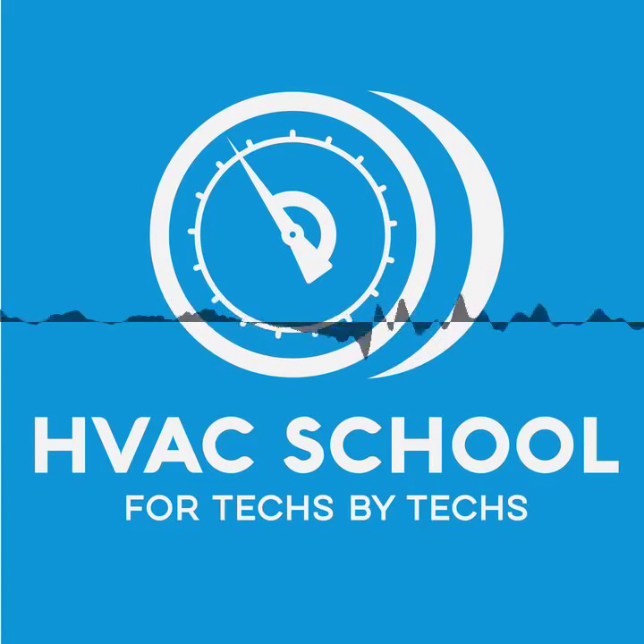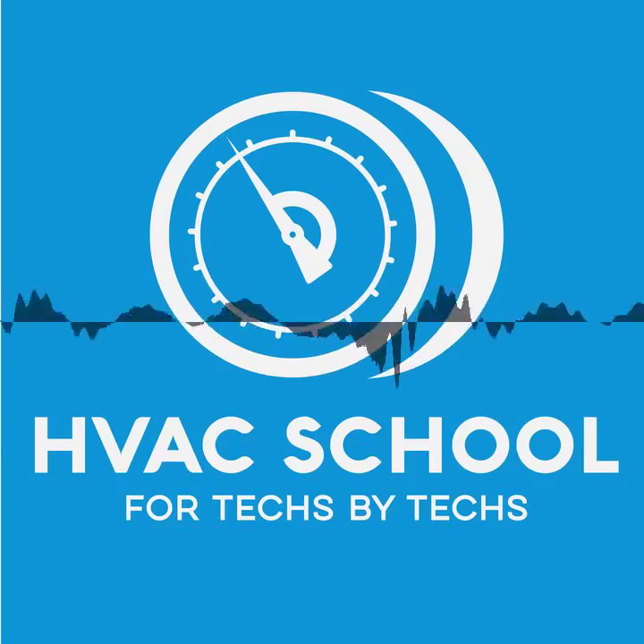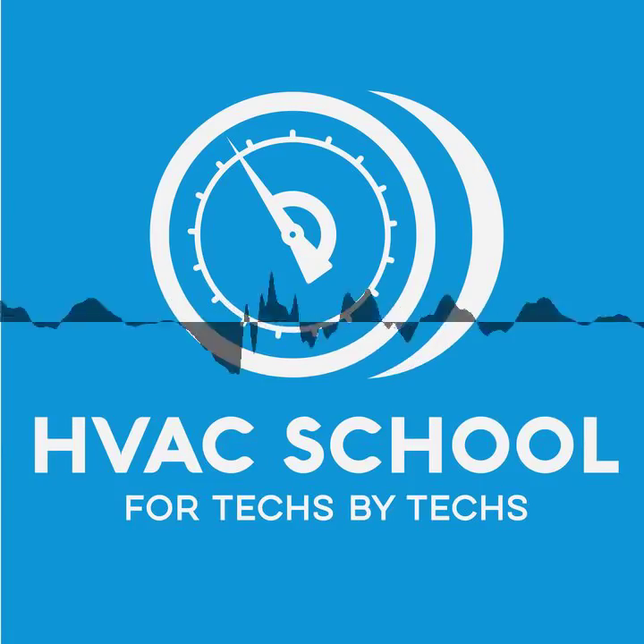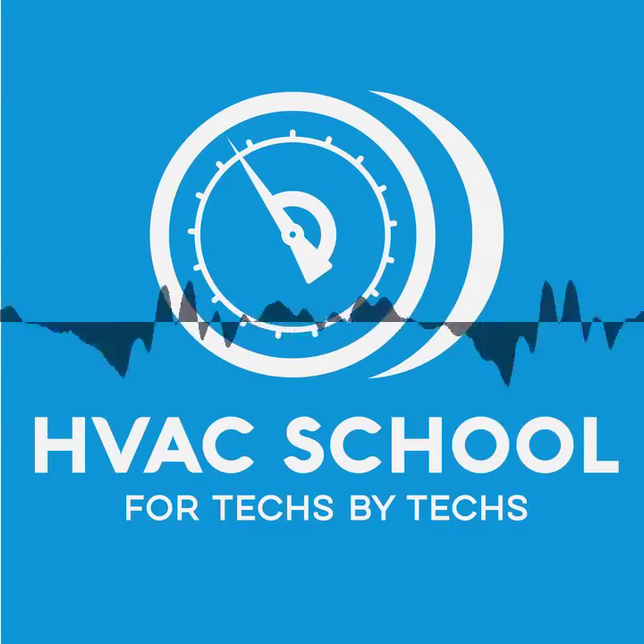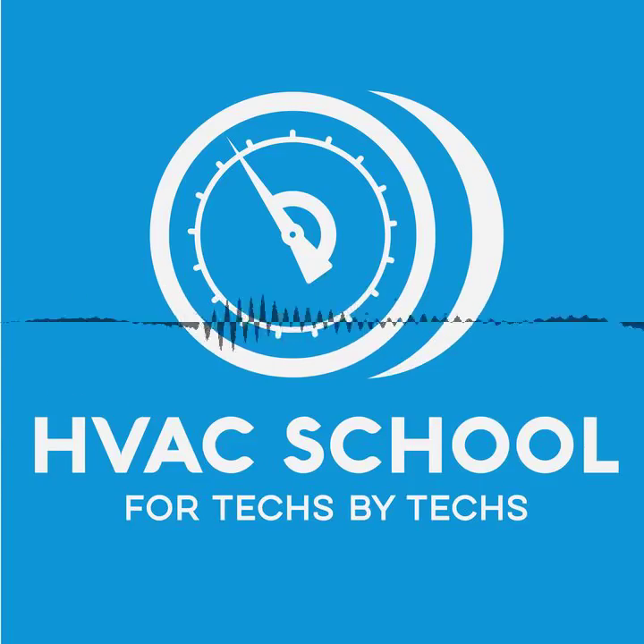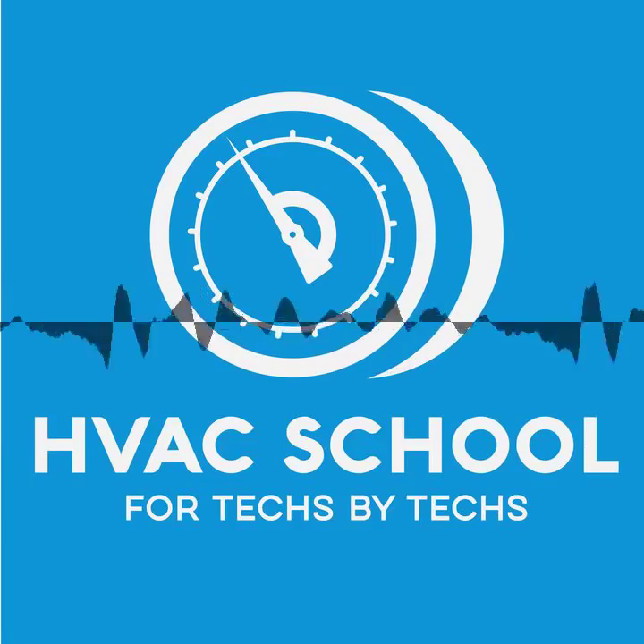When you give it that pressure drop, which is the job of the metering device, then it expands on the other side and it begins to expand into a vapor. So it starts to make that change. And in fact, what it's doing is boiling. All right, so now let's go through and talk about each component and what each component actually does. Okay, what the job of each component is.